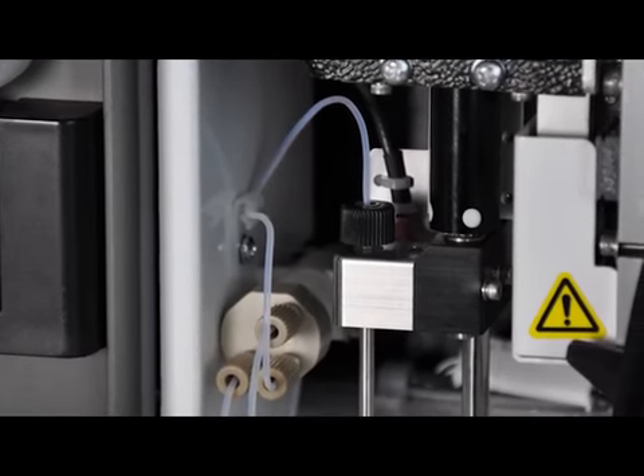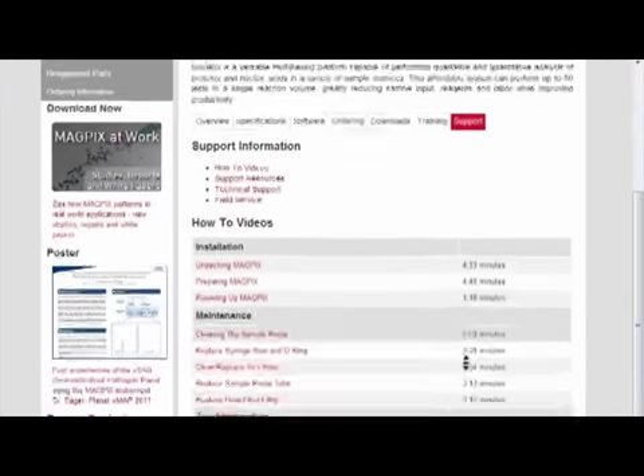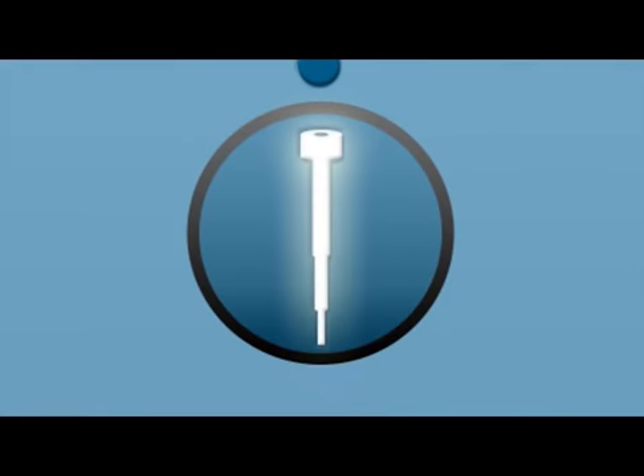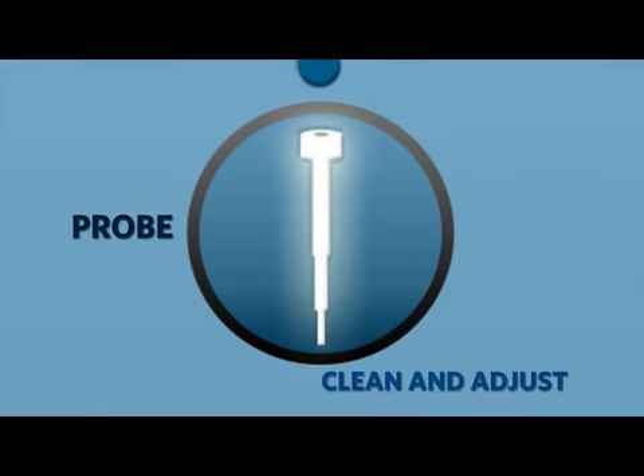Removing the probe to clean it does two things. First, it removes any clogs the probe may have, and second, resets the probe height when you replace the probe. Both of these can cause issues with the proper functioning of the MagPix instrument. For instructions on how to remove the probe and clean it, see the Cleaning Sample Probe video on the Support tab of the MagPix instrument page, or refer to the MagPix User's Guide. This video also includes adjusting sample probe height.